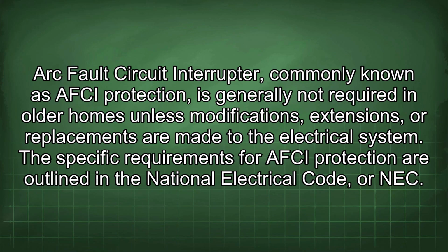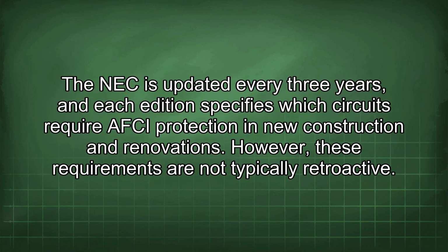Arc fault circuit interrupter, commonly known as AFCI protection, is generally not required in older homes unless modifications, extensions, or replacements are made to the electrical system. The specific requirements for AFCI protection are outlined in the National Electrical Code, or NEC. The NEC is updated every 3 years, and each edition specifies which circuits require AFCI protection in new construction and renovations. However, these requirements are not typically retroactive.